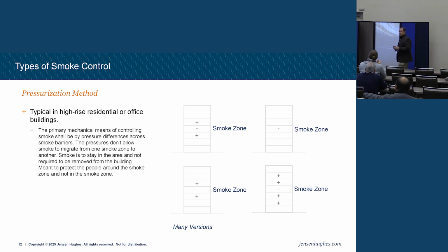So it is common in high-rises not to evacuate the entire building necessarily, right? We do the fire floor, floor above, floor below. So it starts getting complex. Now to do that, right, we're not putting in a cheap fire alarm system that somebody bought from the local supply house. These are big fire alarm systems listed for this application. It's called a UUKL listing. And they are very complex. The sequence of operations is complicated. It trips lots of other systems. Sometimes they are directly integrated with building automation. I don't like those as much, but it can be done. So understanding the system you have in your building is pretty critical, and we'll talk about how you know what you have here in a little while.